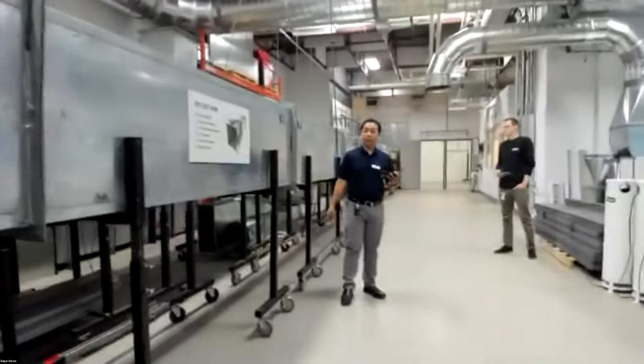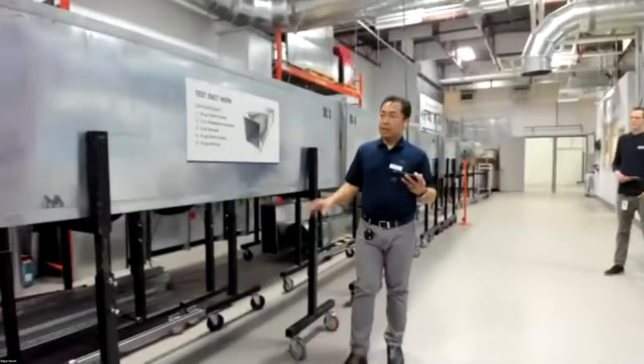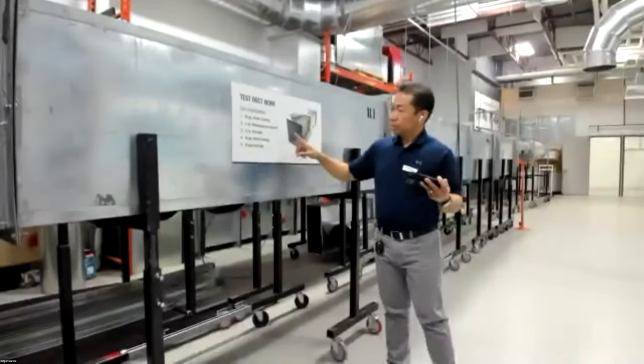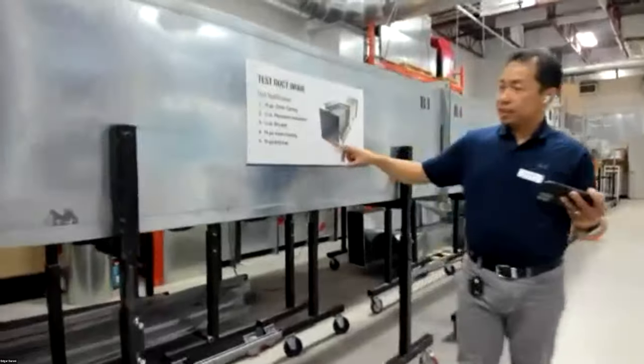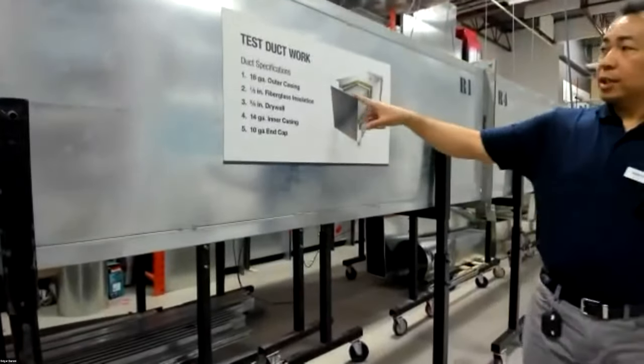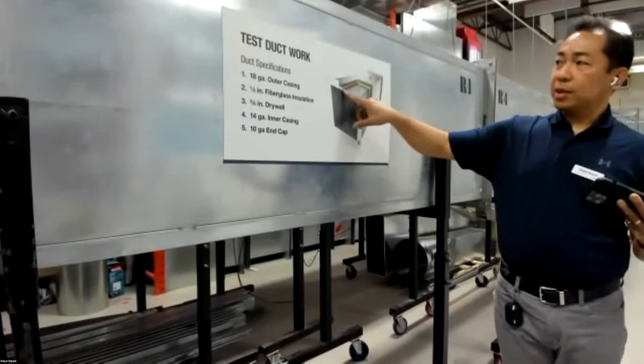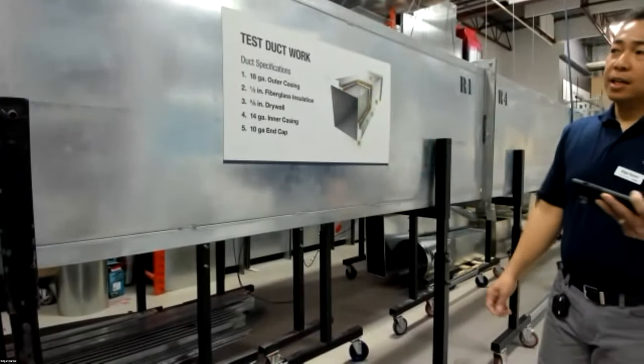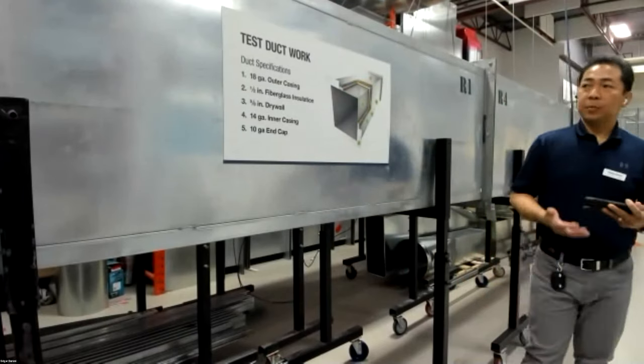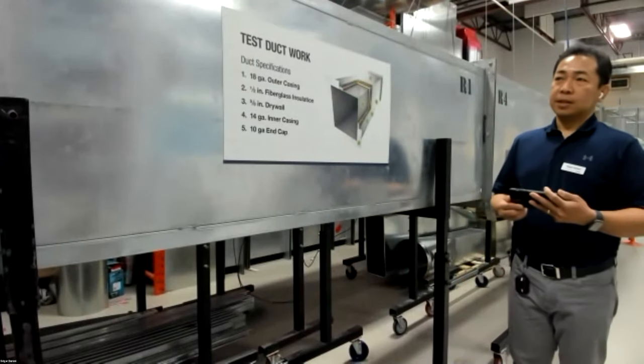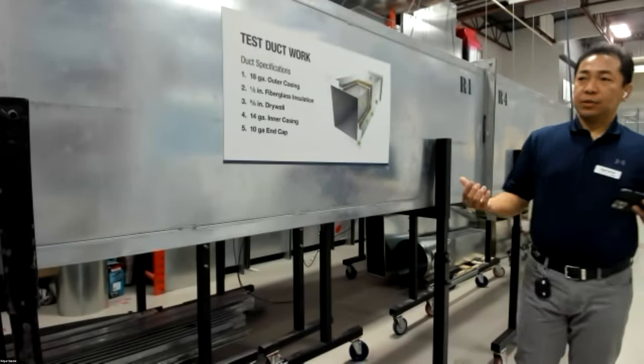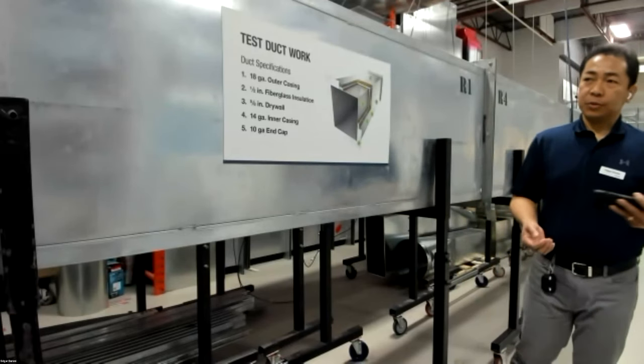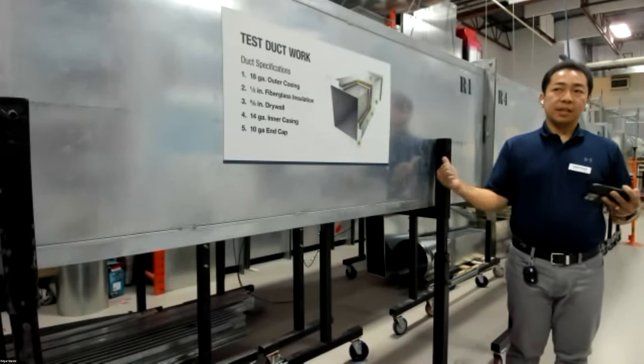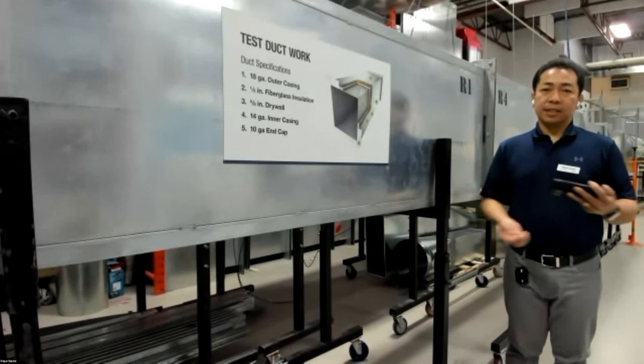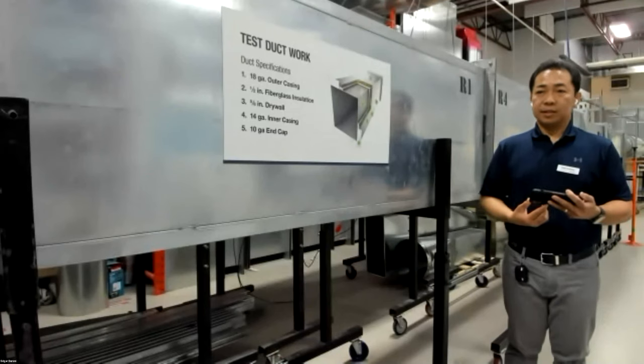So this is our duct system. We have a 24 by 24 ductwork. The duct specs is about 14 gauge inner casing. We have two sets of drywall, two sets of insulation, one set of drywall, and 18 gauge outer casing. The purpose of this test duct is to isolate the flanking noise from the system, so we don't want the noise to be coming in and out of the, or bypassing the silencer unit to be tested.